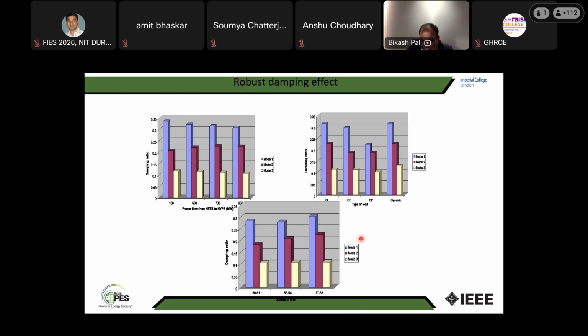If the frequency is a little bit higher, say 0.6 hertz, with 10% damping, then the oscillation will settle even faster. At 0.6 hertz, the frequency is high, so it's only a couple of cycles of that oscillation, then you reach the settling time. So higher frequency means every cycle will take lower time. So 4 times this time constant would be lower time. So that means with a higher frequency, you can even afford to have a damping of say 0.08, 0.09.